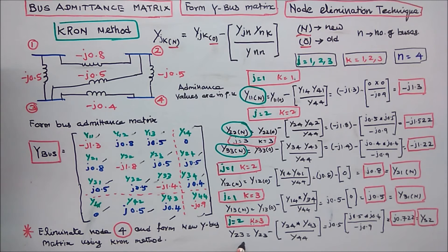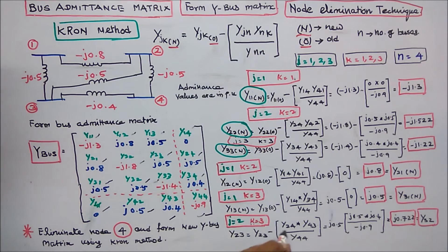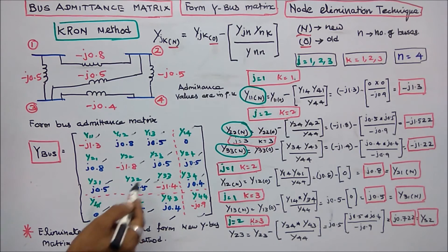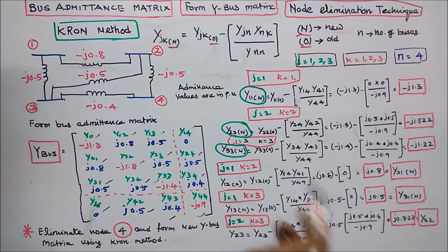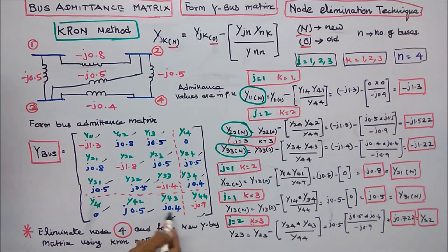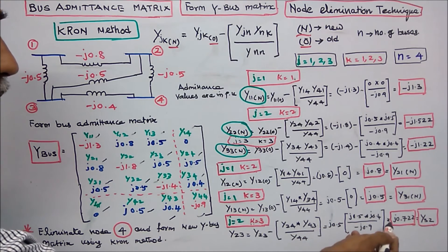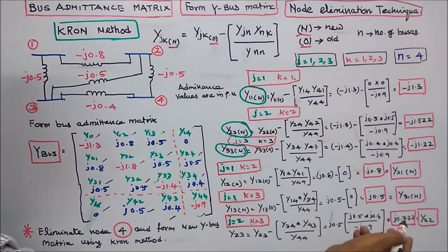For j=2, k=3: Y23(new) = Y23(old) minus Y24 times Y43 divided by Y44. Y23(old) is plus j0.5, Y24 is j0.5, Y43 is j0.4, divided by minus j0.9, giving Y23(new) equal to j0.722. By symmetry, Y32(new) equals j0.722. The off-diagonal elements are now complete.